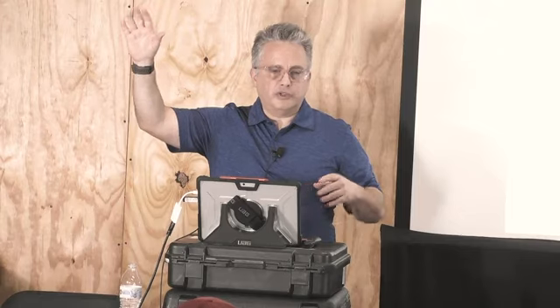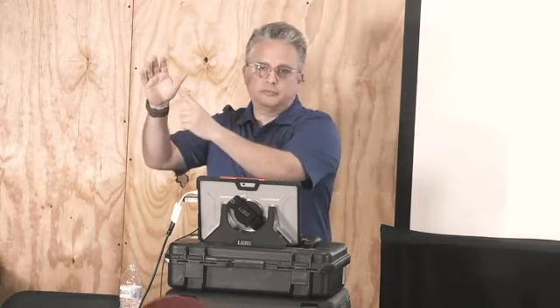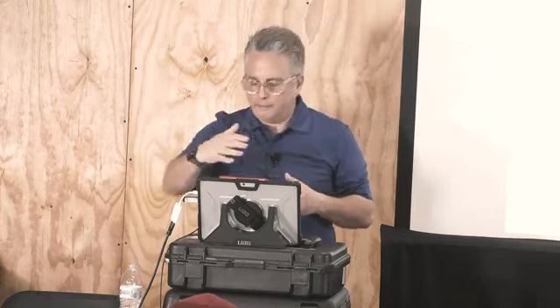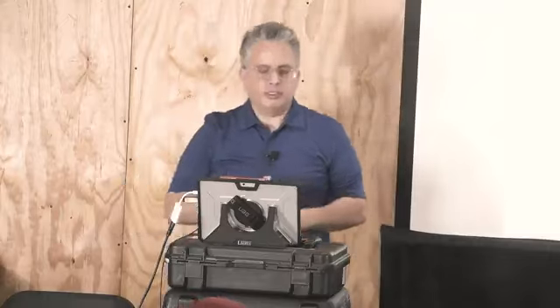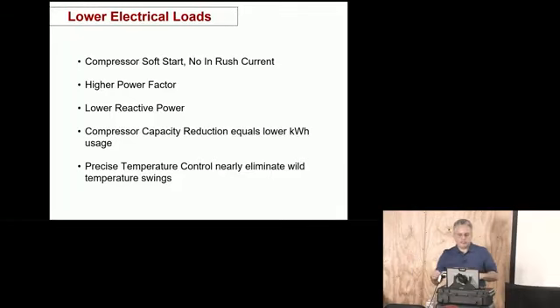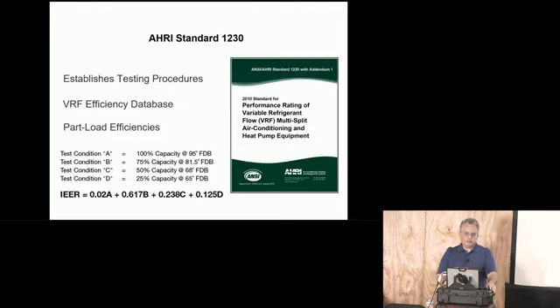For instance, if you install an indoor unit and it's a high wall unit, and a certain part of the day the sun beats on it, well, it's going to overcool, right? Because it thinks it's too hot. You have to strategize where you're going to be sensing temperature. With these systems, you can sense temperature from the indoor unit. You can sense temperature from the remote. You can have a remote sensor. So you have a number of choices.